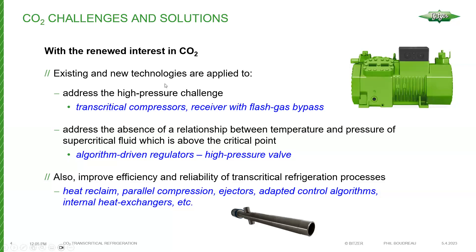In order to fully exploit CO2, existing and new technologies are applied to address the high-pressure challenge. We needed to develop transcritical compressors — basically high-pressure reciprocating compressors. Another technology that fits well in the CO2 transcritical world is the receiver with flash gas bypass. We also need to address the absence of a relationship between temperature and pressure of the supercritical fluid above the critical point — this led to what I call algorithm-driven regulators, called high-pressure valves, sometimes referred to as 'magic valves' in the industry. CO2 transcritical is not really considered efficient right from the start.